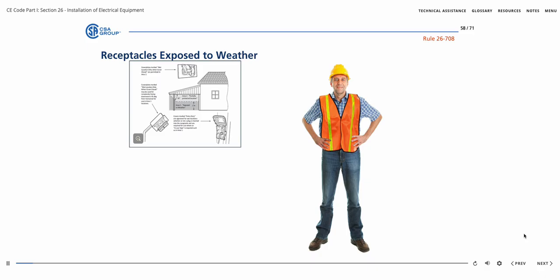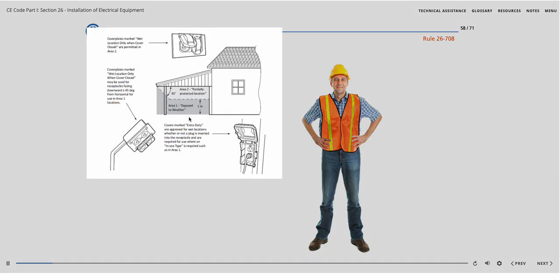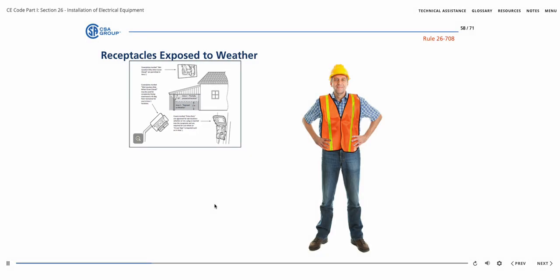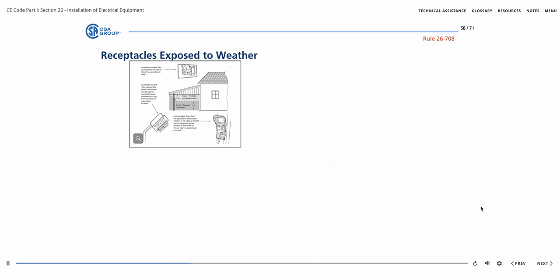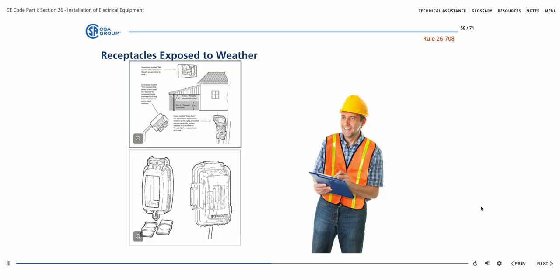Receptacles provided on the outside of buildings that are exposed to weather are generally used for outdoor appliances that typically get used when the weather is good. The wet location only when cover closed, weatherproof covers, or the equivalent, when required to be used on these receptacles, only keep the moisture from entering the enclosure and or the receptacle when the appliance plug is not inserted into the receptacle, such as when the cover is closed. The reality is that there are many instances when these receptacles are used for items that remain unattended for long periods, such as automobile heaters, electric vehicle charging stations, and seasonal decorative lighting. In such cases, the appliance plug remains inserted into the receptacle, which leaves the weatherproof cover open, exposing the receptacle to all types of weather conditions.